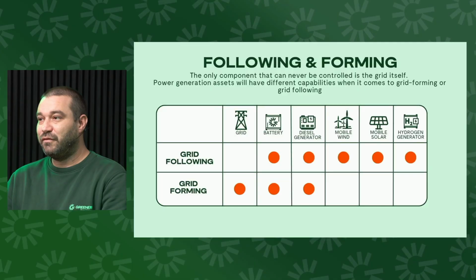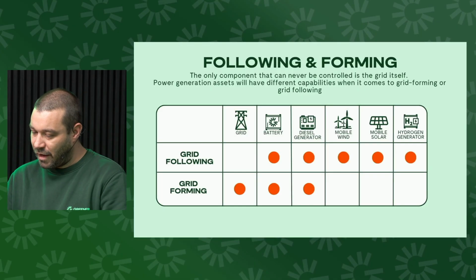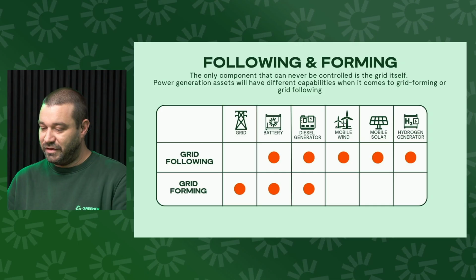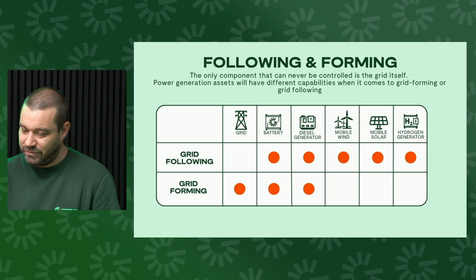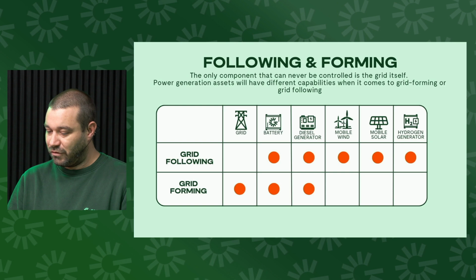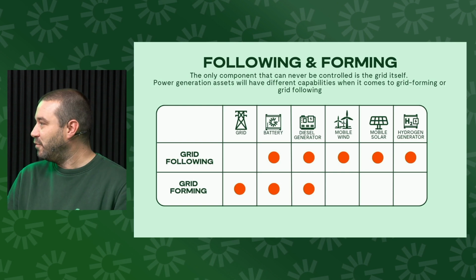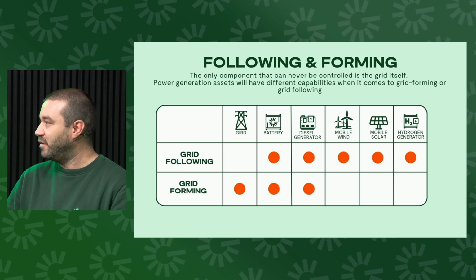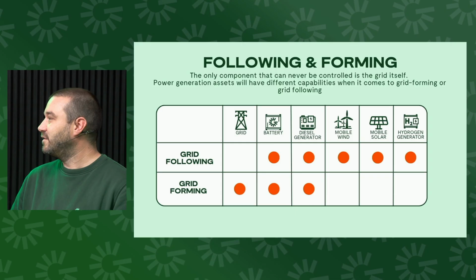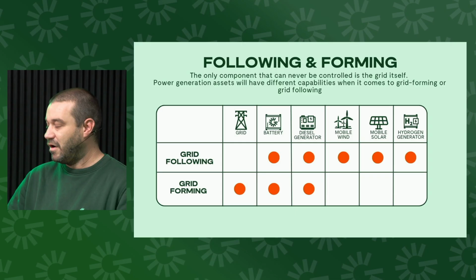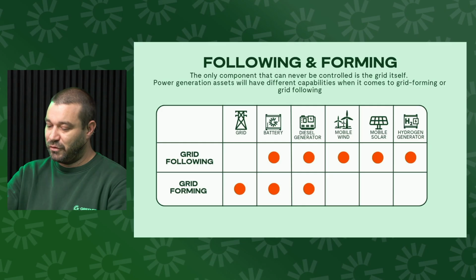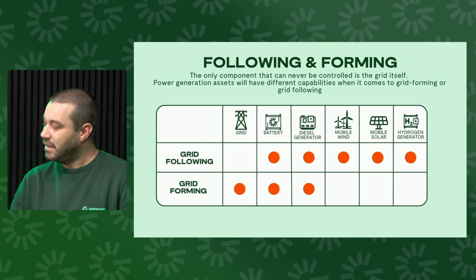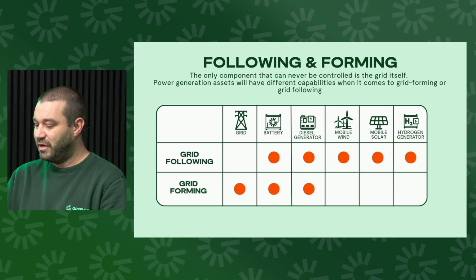Looking at grid forming and grid following, as we said before, the only thing we can't control is the grid itself, but batteries can grid follow and grid form, so they can run themselves, they can form a grid by themselves. Diesel generators can do the same. They can form a grid and run, but they can also follow a grid, connect to, and then push power into a grid. Mobile wind would follow, solar would follow, as would hydrogen.